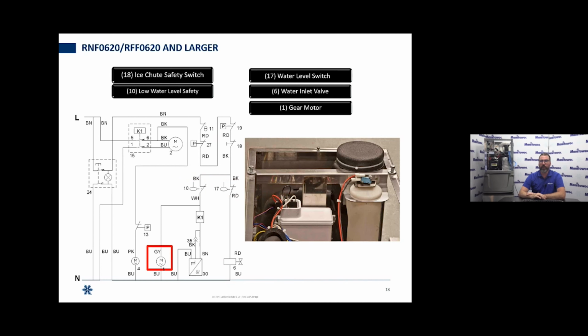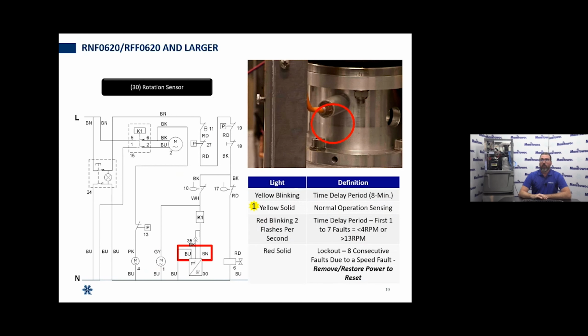And of course, we have our gear motor, and that gear motor is what's going to auger the ice out of the evaporator once that ice is formed. Rotation sensor, I just brought this up earlier, a couple slides ago. Here on the 620 and all larger machines after this, we're going to bring in a rotation sensor. This rotation sensor is essentially checking to make sure that the auger inside the evaporator is turning and in fact moving. So if we have a failure with the gear motor, we're going to lose RPM. That rotation sensor is going to sense that and shut that machine down. Of course, we don't want to be running a refrigeration system if we don't have a working auger system in the evaporator. We're just wasting energy at that point.